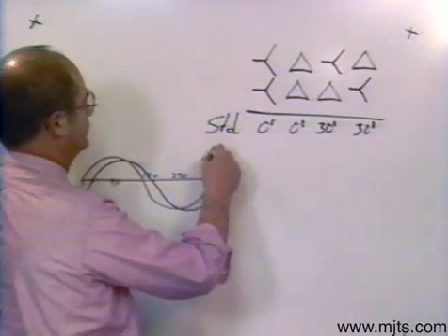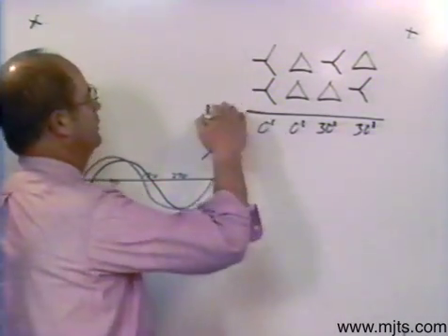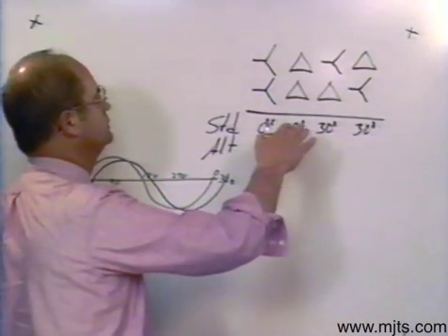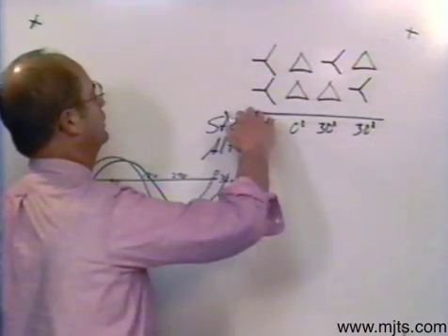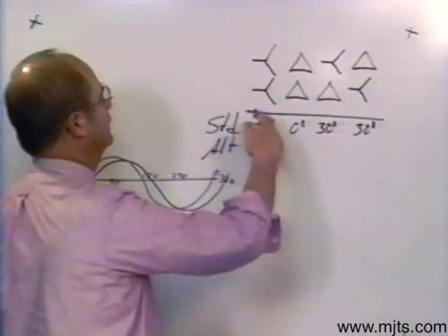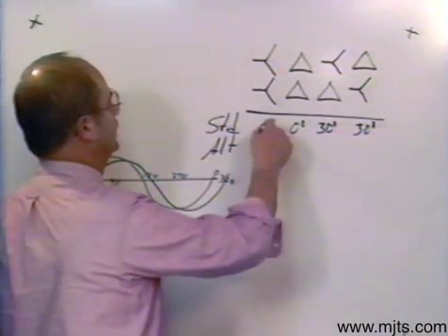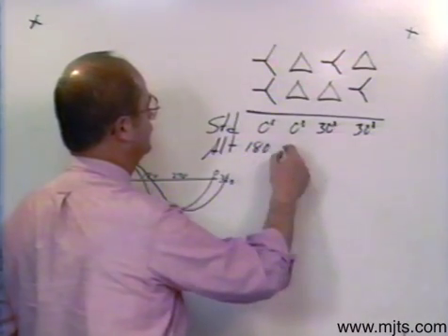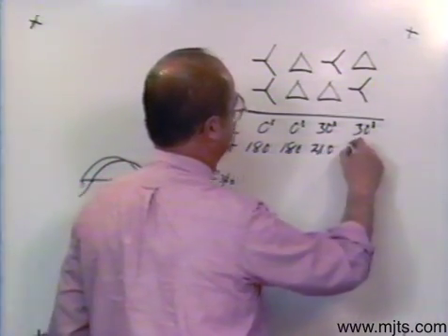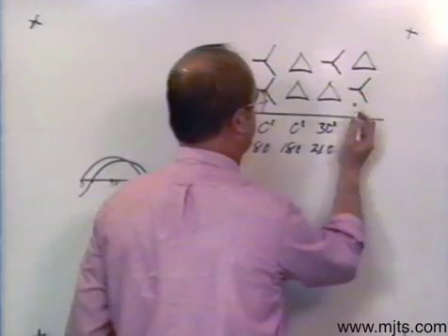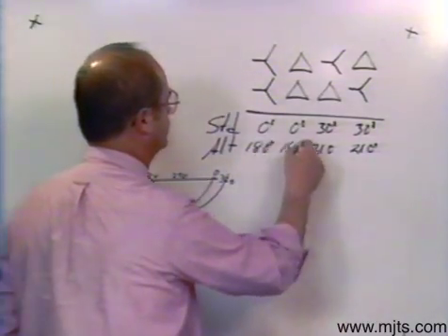Now, we call this least possible displacement standard. Those are the standard displacements. The alternate displacement: any of them you can go 180 out, which means current flow is just in the opposite direction. I could be 0 degrees or 180, 0 degrees or 180, 30 degrees or 210, and 30 degrees or 210. Those are the possible displacements.